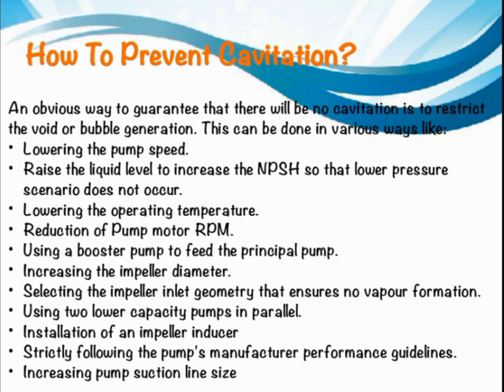Let's see how to prevent cavitation. An obvious way to guarantee that there will be no cavitation is to restrict the void or bubble generation.